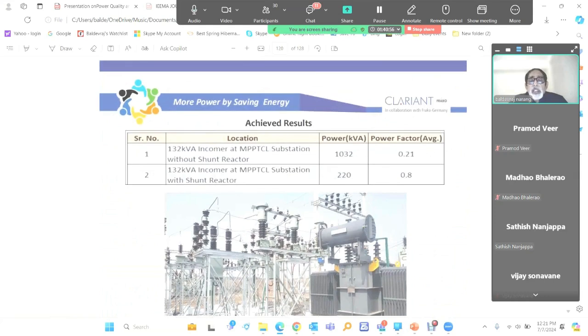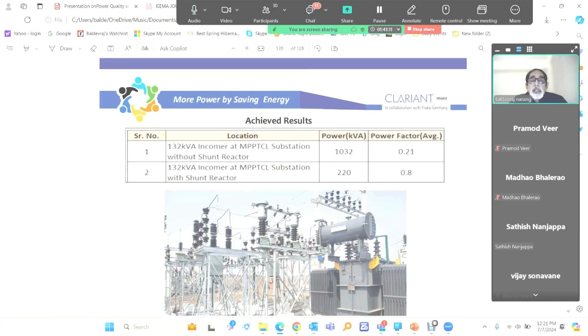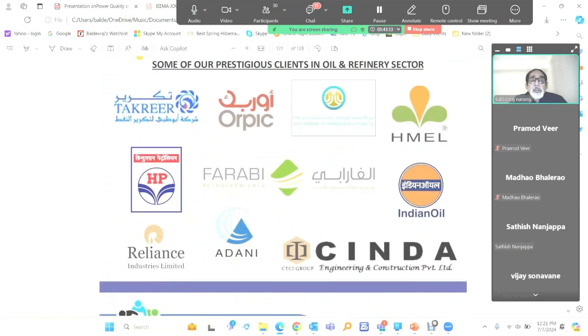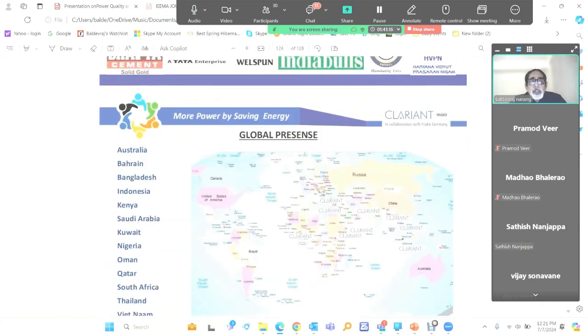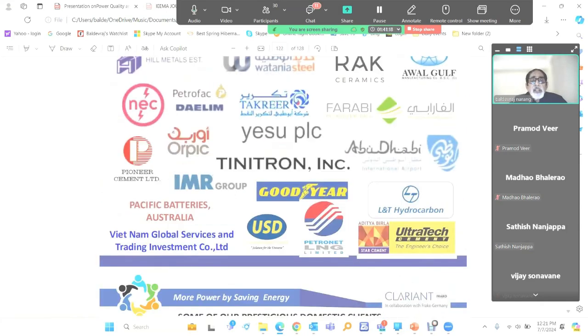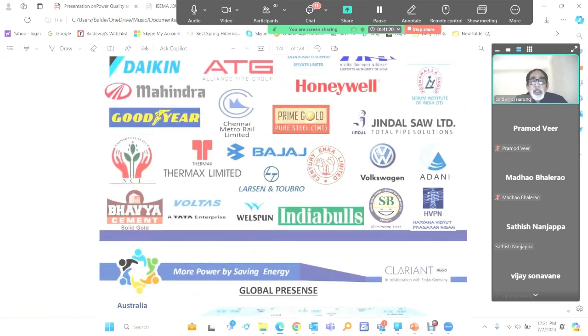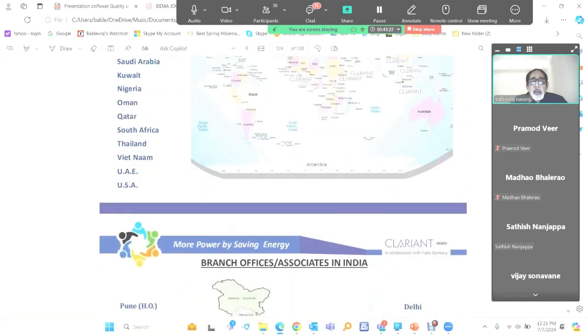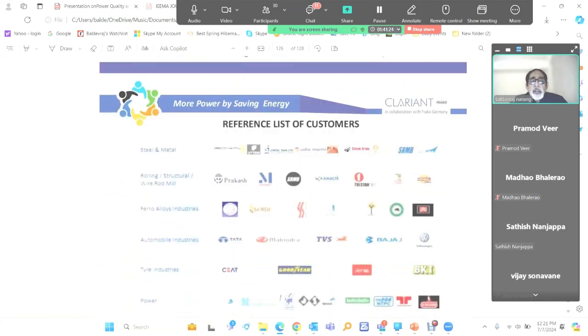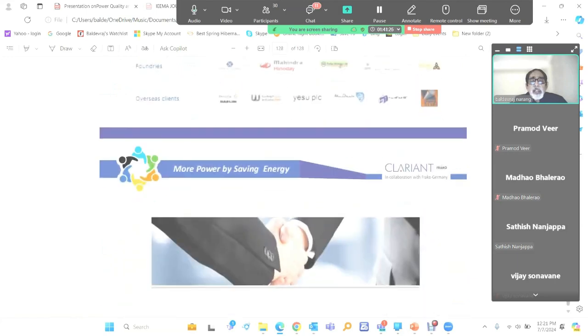So this is what I was telling about Vector Green. The power factor was very poor and the demand was very high. Demand was brought down from 1000 to 200 something. Power factor went from 0.21 leading to 0.8 or in fact 0.9 afterwards. So all penalties were removed. So these are our clients in India as well as overseas. And then references are there.